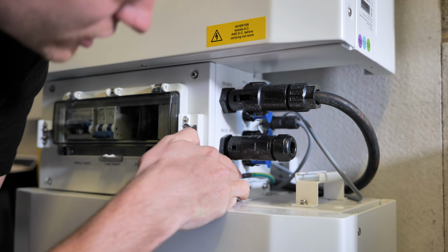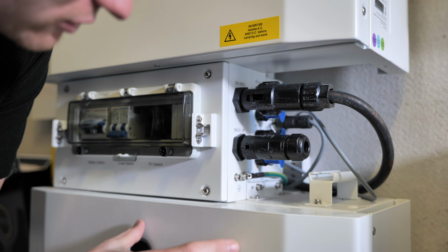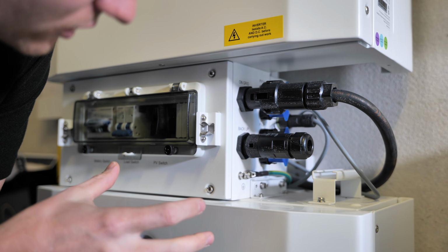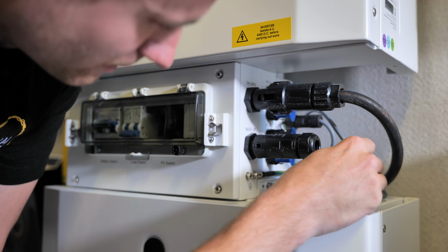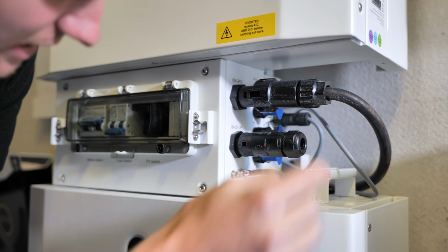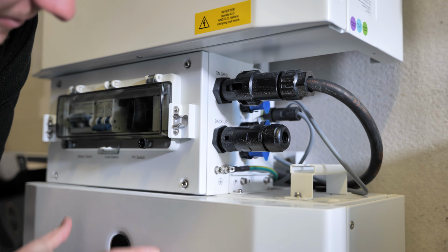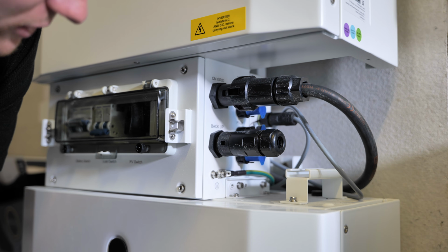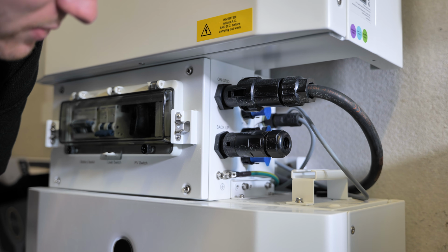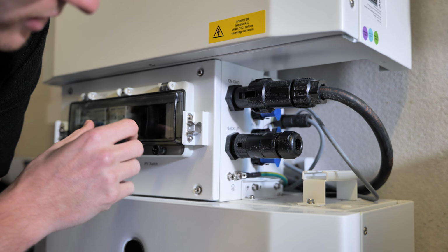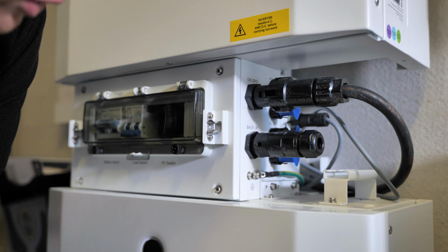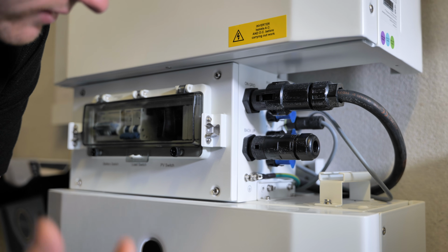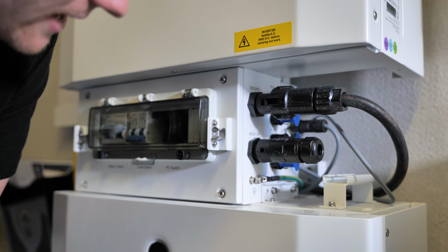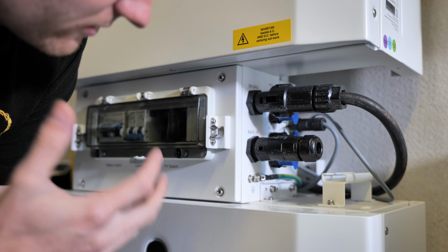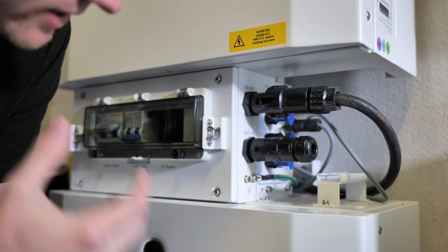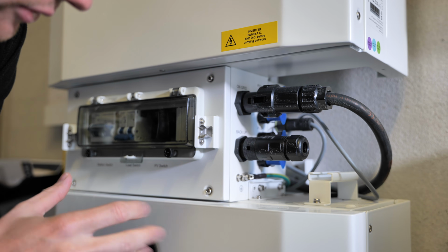We've then got an earthing connection here, which just earths the battery modules and the inverter and links it all together. And then we've got the battery BMS cable just here as well. That goes down to the batteries and basically feeds the information from each one of the battery modules' BMS, which is battery management system, into the inverter, so the inverter knows everything's okay, what the state of charge of that individual cell is, what the cell voltages are, all the information the inverter needs to keep those, in this case, 4 battery modules nice and healthy.